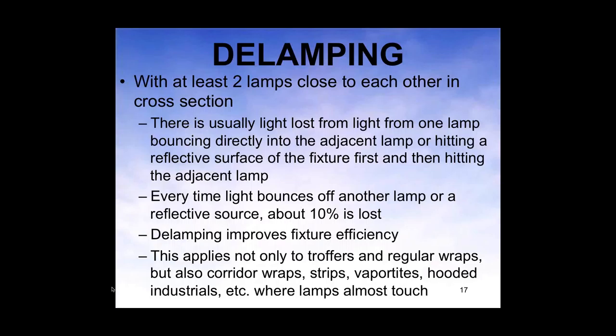There's also the photometrics. If you have lamps next to each other in a 2x4 trough or 4-lamp fixture, you're going to lose a lot of light from one lamp shining into the adjacent lamp or hitting a reflective surface and then hitting the other lamp. If you reduce the number of lamps, you improve fixture efficiency. Every time a light ray hits something and bounces off, you lose about 10%. This applies not just to troffers and wraps, but also corridor wraps, strips, vaportites, industrials — almost any time lamps are very close to each other.